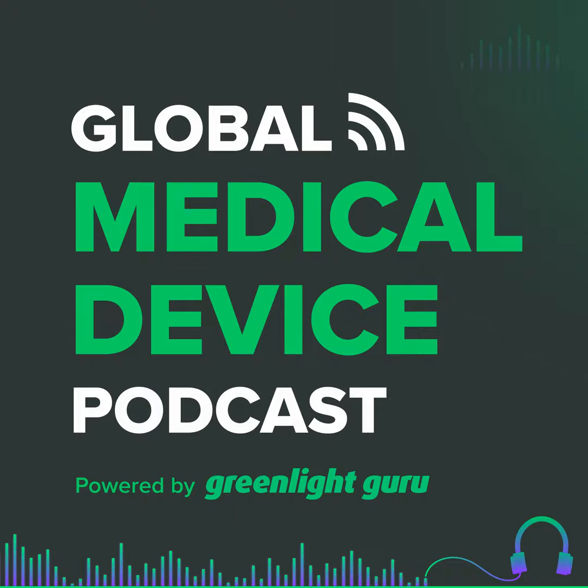The second reason why I make the recommendation to take an NSR device to the FDA, even when it's not required, is to avoid a very common problem where a company does a clinical trial, they get approval of all the IRBs and everything else, they submit their 510K or the de novo or whatever it is. FDA says this looks great, but we want this additional information. And now, maybe they want some additional clinical endpoints or something like that, or a higher power of the trial.